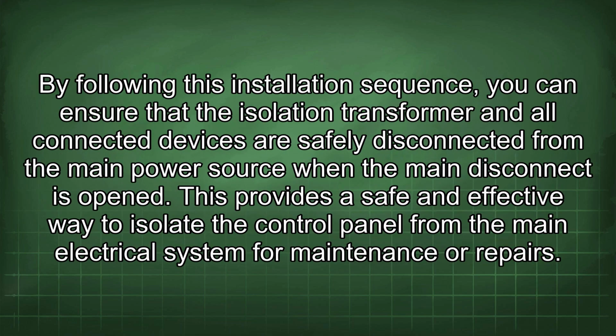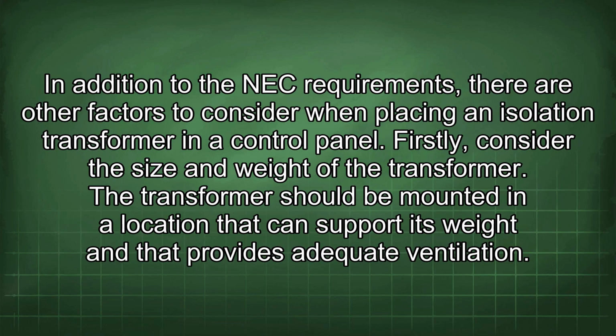By following this installation sequence, you can ensure that the isolation transformer and all connected devices are safely disconnected from the main power source when the main disconnect is opened. This provides a safe and effective way to isolate the control panel from the main electrical system for maintenance or repairs. In addition to the NEC requirements, there are other factors to consider when placing an isolation transformer in a control panel. Firstly, consider the size and weight of the transformer.